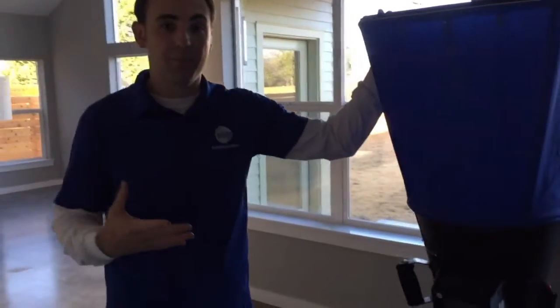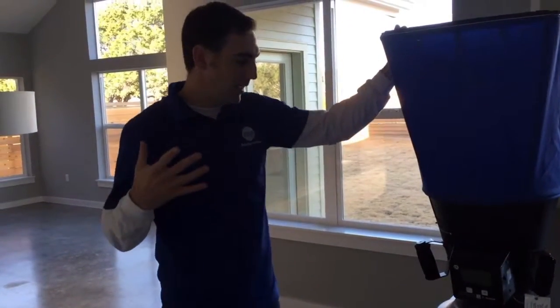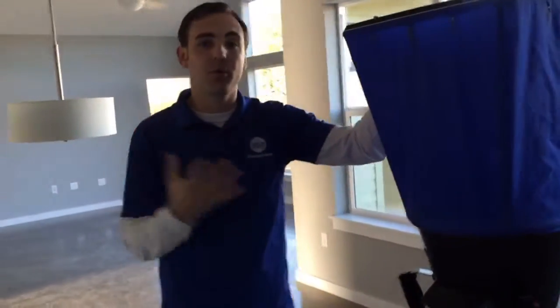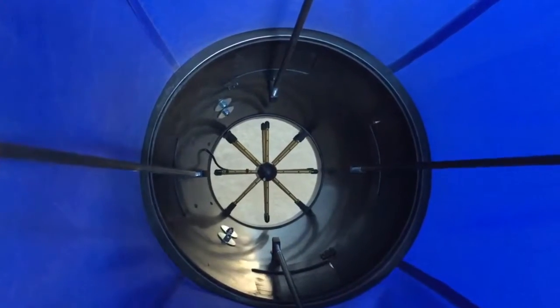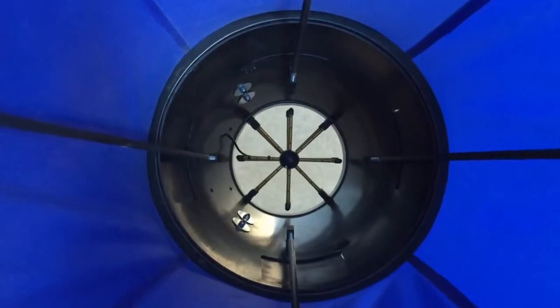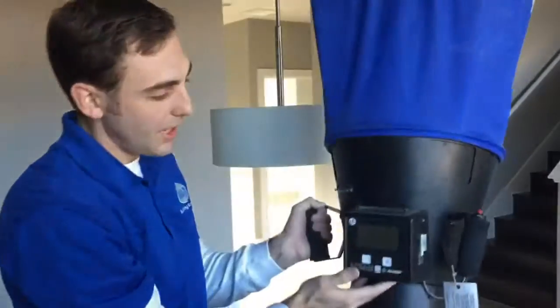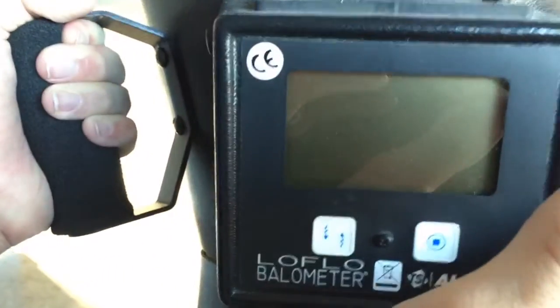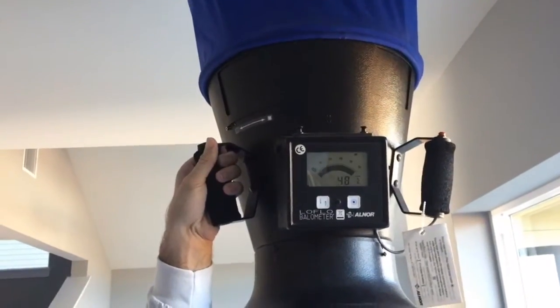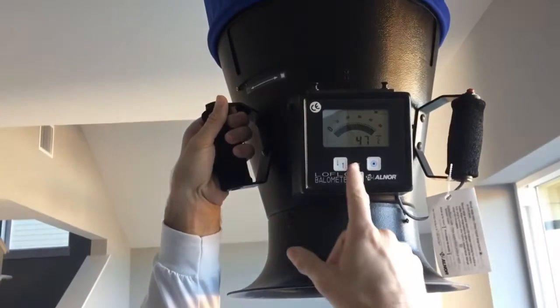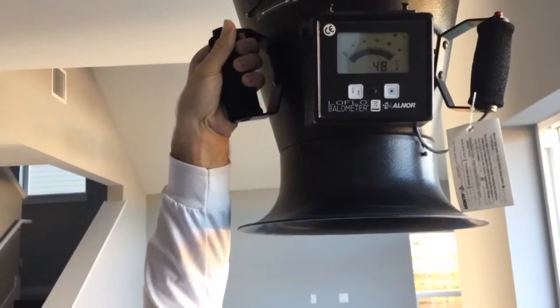This is a balometer. It's my preferred choice in measuring airflow. It is not the most accurate thing, but it is the most usable, the most versatile, and provides numbers that are well within any margin of error. So this is sort of the gold standard when it comes to airflow testing in code testing like this with new construction. Inside there are vanes that are measuring the pressure of the air going through one side and out the other. And that's a known opening, so then it can calculate the volume of air that's going through based on the pressure. It has a digital readout right here, and so when we put it up to a vent, like so, we can then turn it on and measure the amount of pressure that comes through, which converts into a CFM. Currently there's 47 CFM, cubic feet of air per minute, coming through this duct.